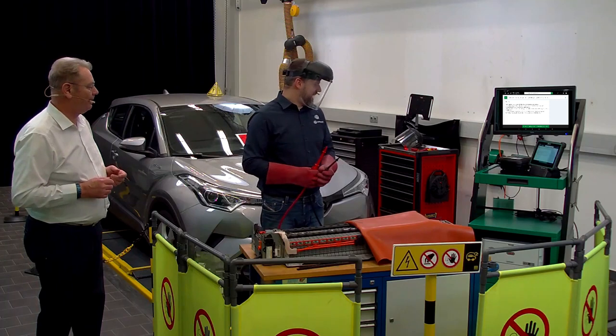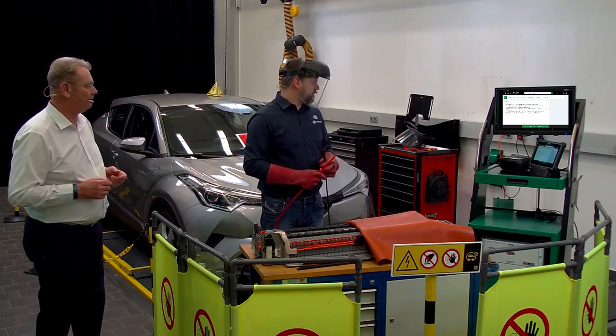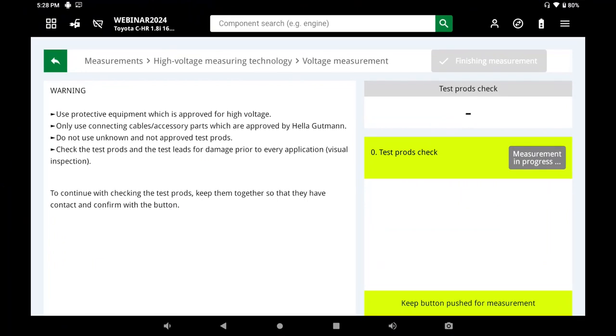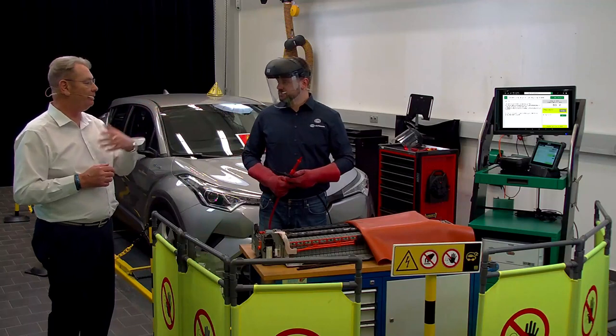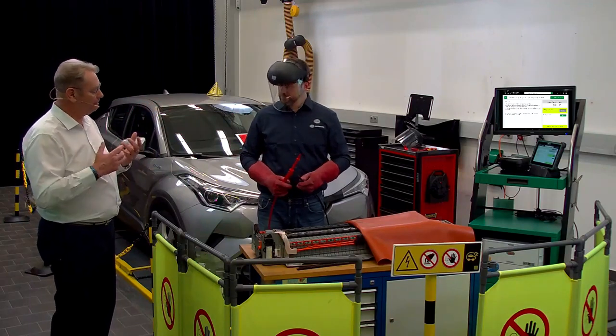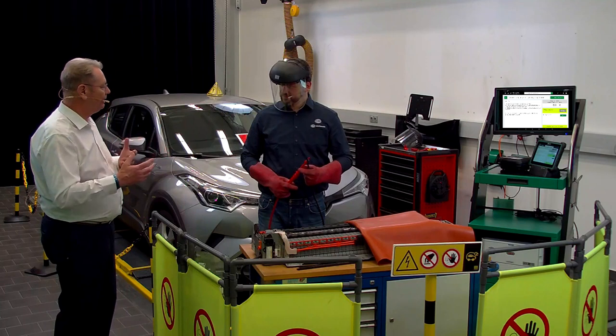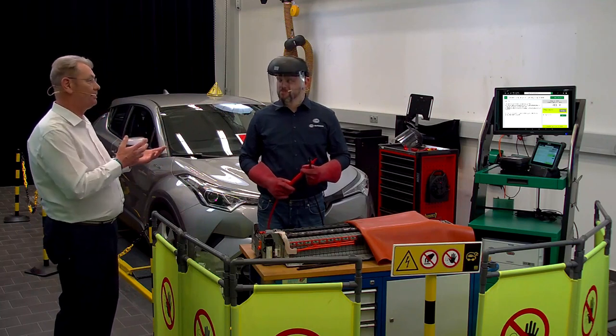Very good. What I've done now, I have skipped this page, and what we do now is a test probe check. So I put both test probes together and push this button, and the system creates an automatic test probe check to be sure that the system is totally okay and ready for use, from the test probe on the plus side to the test probe on the minus side. And we get a green okay, and every measurement we do will get a green okay or not okay, depending on how you interpret it.